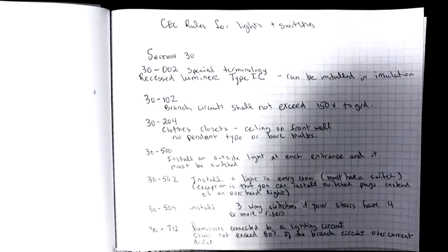30-102 tells us that branch circuits for lighting shall not exceed 150 volts to ground in a residential unit.